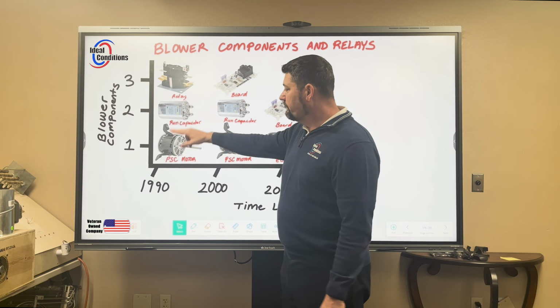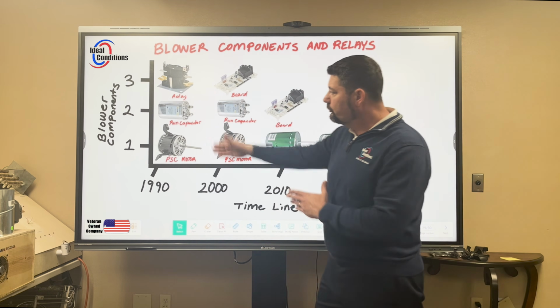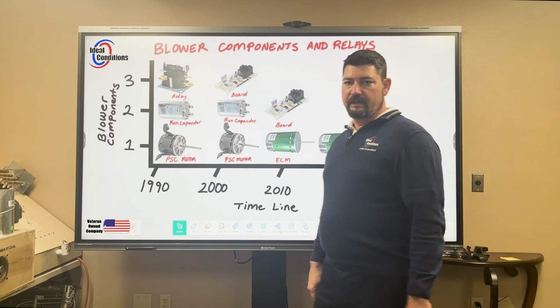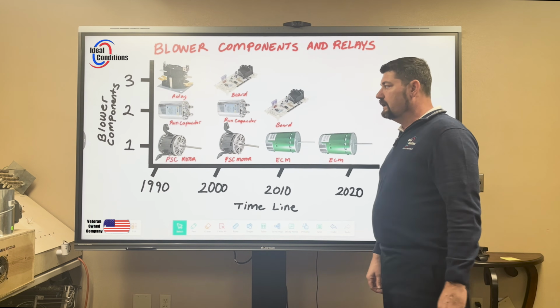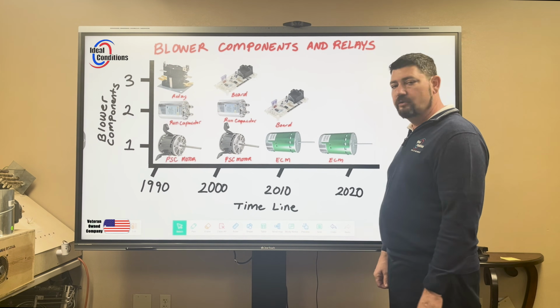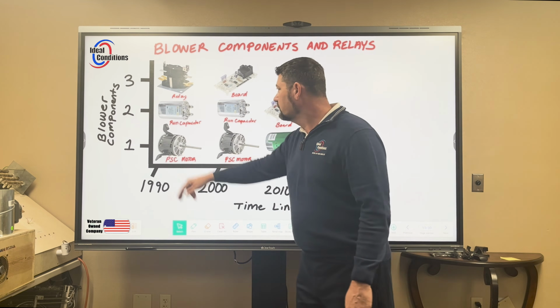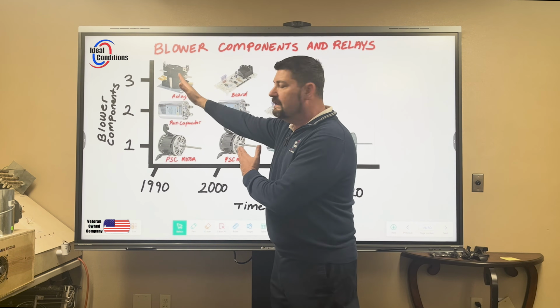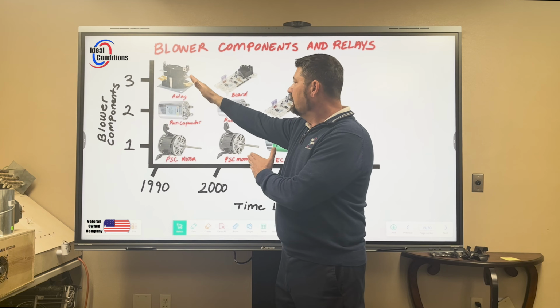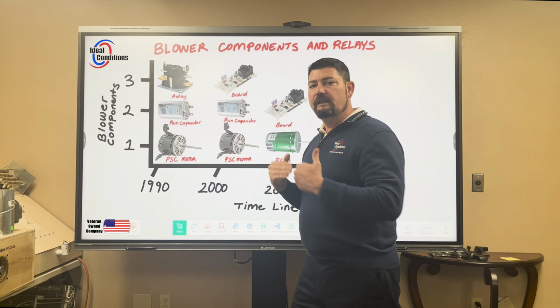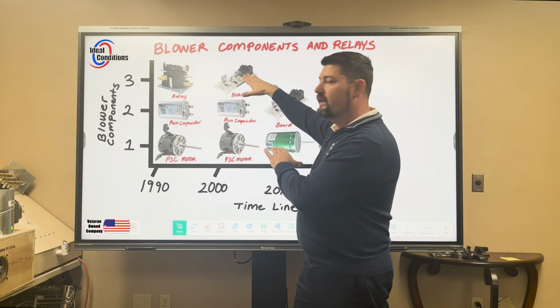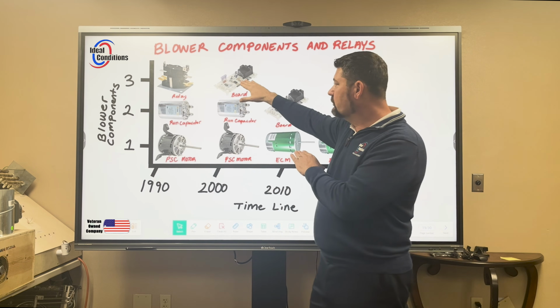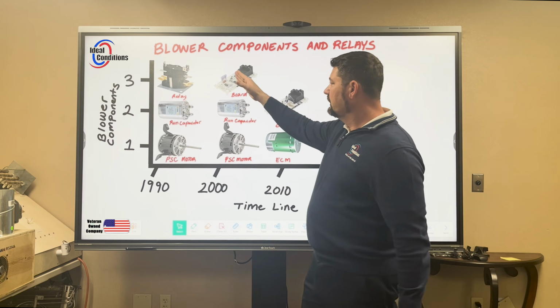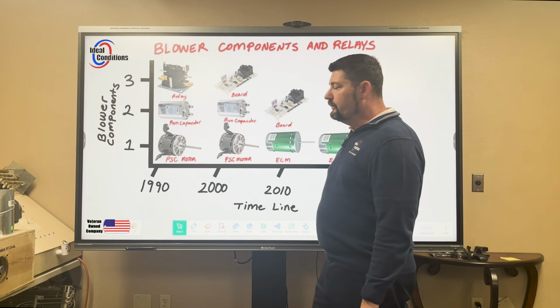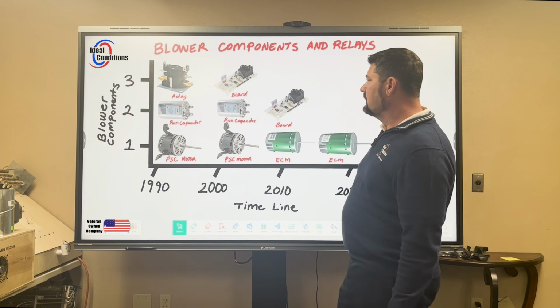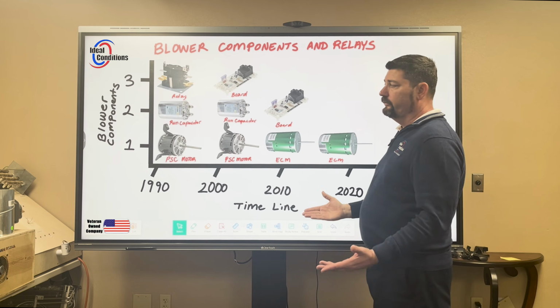We have a run capacitor PSC motor, and we use those three components in the middle of our video to show you how we chose to wire up two different speeds on our PSC motor. Once we leave this relay, if we want an on-delay or off-delay, we have to go to a control board. That's what these control boards do, plus they've integrated the fuses into them and whatnot, and we're going to go over those soon.